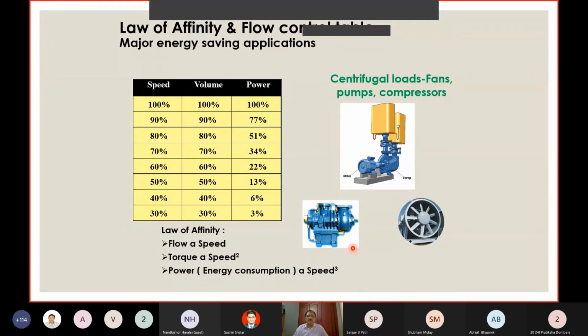Normally, all these equipments are oversized, and in the plant, people use them variably for their requirement by using a damper or a valve. So wherever you find an application where a damper or valve is used, you should go for VFDs, because the VFDs will give you substantial energy saving.